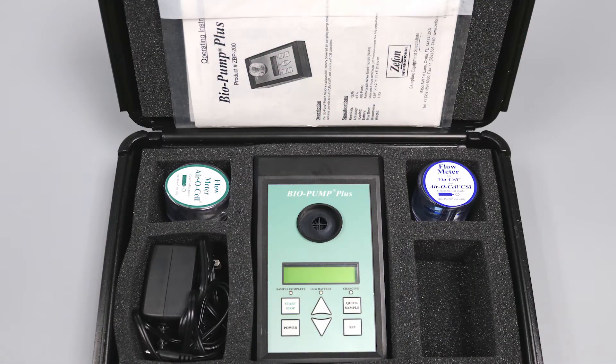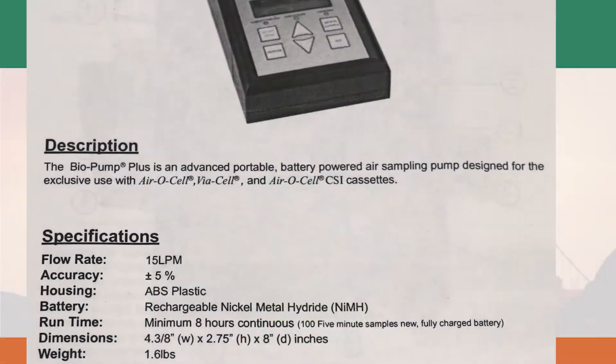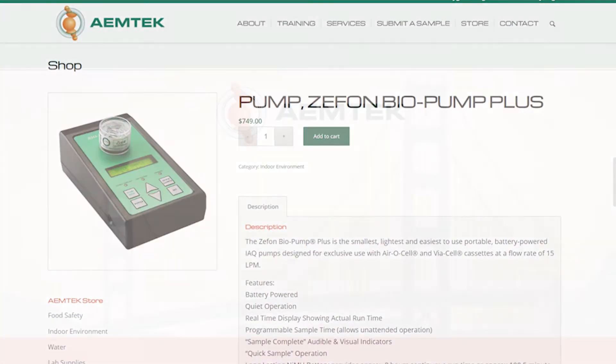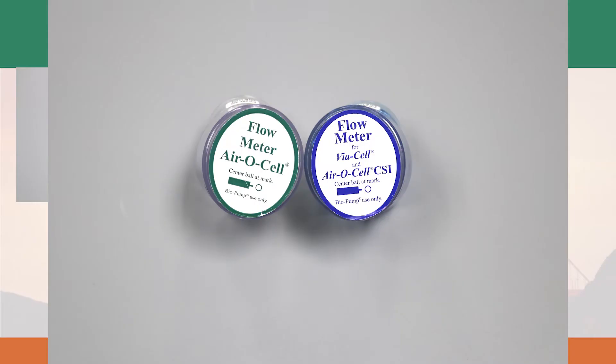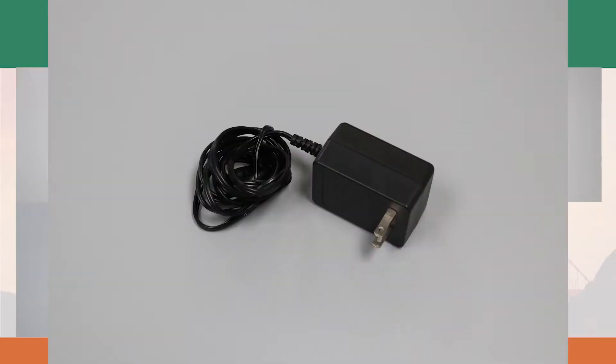Here is the Zefon BioPump Plus. It is an air sampling pump designed for exclusive use with Air-O-Cell and Via-Cell cassettes with a 15 lpm. The sampling pump is available for rent at the AEMTEK online store. The sampling kit includes a pump, two airflow indicators, a user manual, and an electric charger.